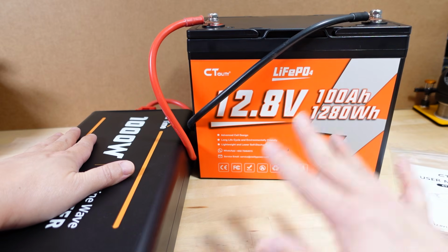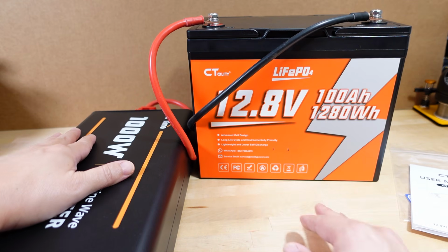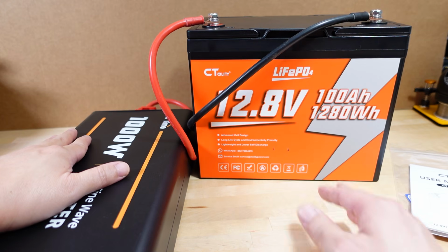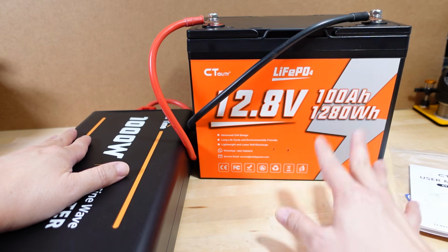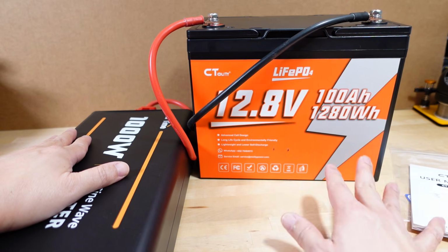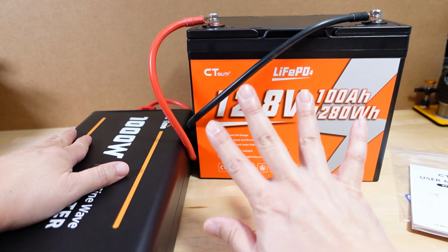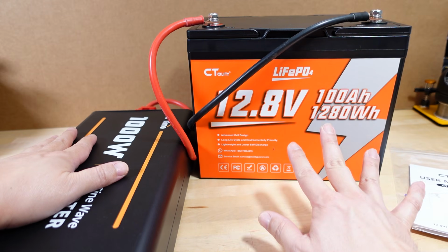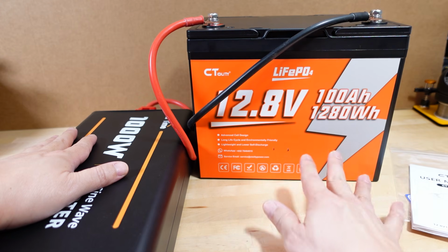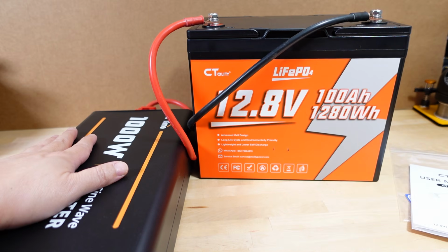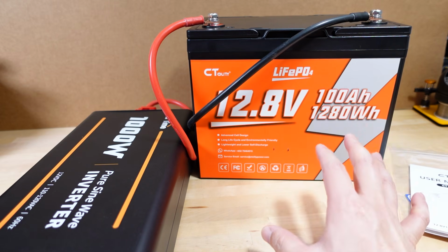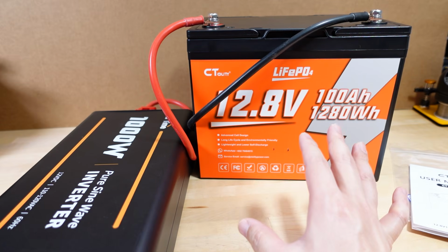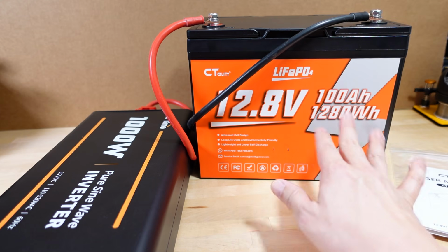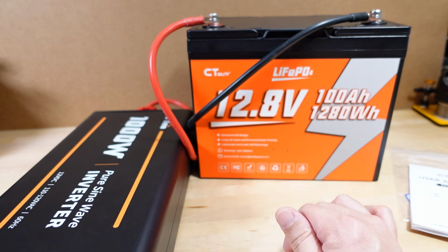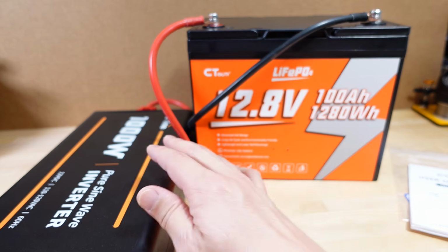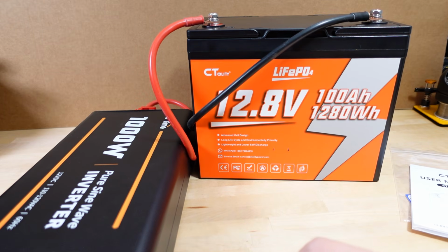Obviously, there's going to be cases where you're going to want to go over for brief periods of time. That's going to be fine, but keep in mind that even at 1,000 watts here, or close to 125 amps, you're going to be drawing this battery down, if you run that at a continuous level, in about an hour or less. While this has a tremendous amount of capacity, if you draw a really high amount of current for a very long period of time, it only lasts about an hour because at the end of the day, it's only 100 amp hours capacity total. So my conclusion at the end of the day is it's a good battery, passed all my tests for what I would expect for this type of battery, 12 volts and 100 amp hours. And as I said, if you keep it under 125 amps total, 1,000 watts in terms of your inverter, you should be good to go with this battery, no problem.